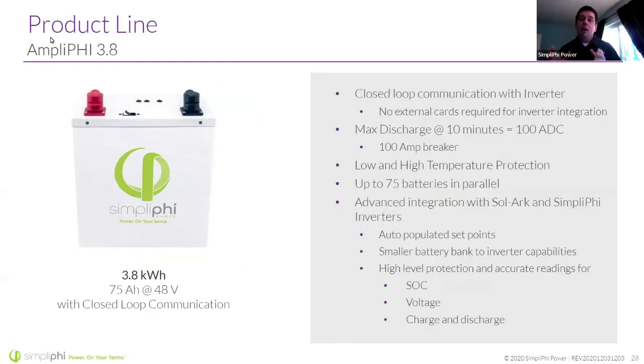Our AmpliPHI battery. This is a more advanced battery management system. It has closed loop communication with a couple of inverters. So basically you're running Ethernet cables from battery to battery to inverter, and that allows the inverter to communicate with the battery. Because of this, like I said earlier, you've got an increased discharge of up to 100 amps DC. We've also got low and high temperature protection, where at those extremes, the battery is able to communicate to the inverter, hey, I'm approaching freezing, and I know I shouldn't be charging as I approach freezing. I need you to scale back my charge rate. I need you to govern my charge rate so that I don't damage my battery cells. A very cool feature. Because of the battery-to-battery communications, you are limited to 75 batteries in parallel. Still a significant bank. And we currently have integration with the Sol-Ark inverters and our SimpliPhi ESS.